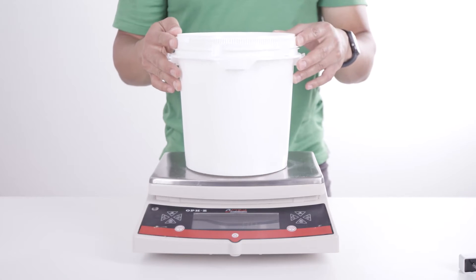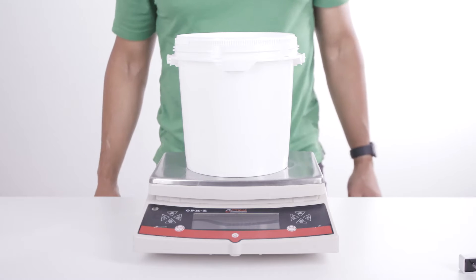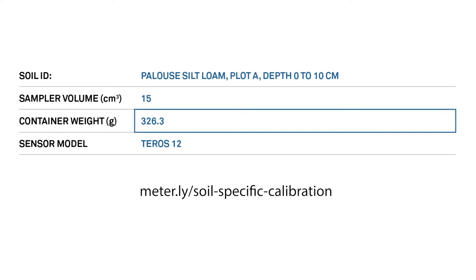Begin by measuring the mass of the clean, dry calibration container. Record the tare mass in the calibration spreadsheet entitled Table 1, Method A. Table 1 can be downloaded at the web address below. It automatically calculates the calibration function after you enter in all the values.